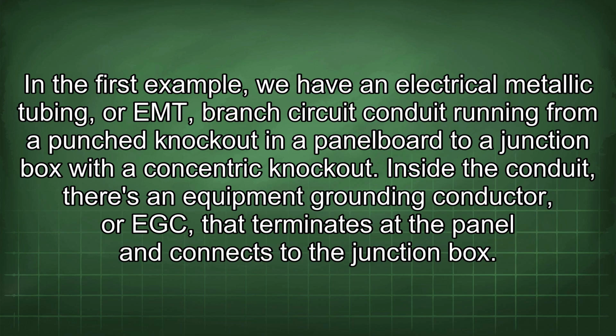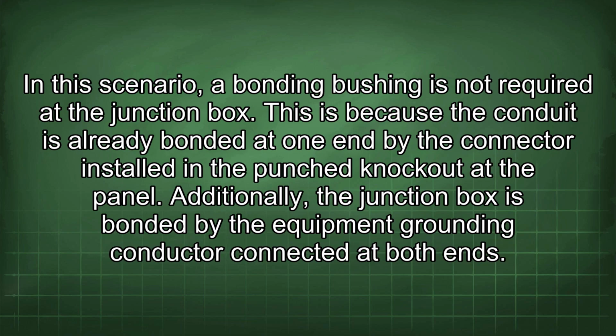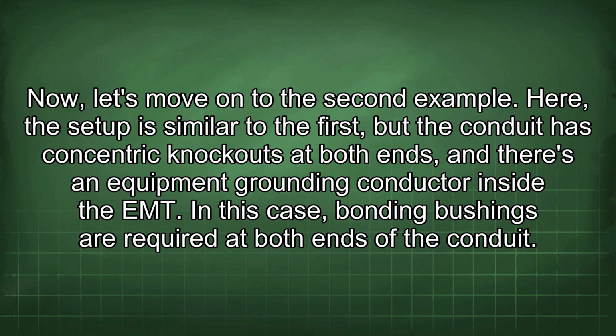Inside the conduit, there's an equipment grounding conductor, or EGC, that terminates at the panel and connects to the junction box. In this scenario, a bonding bushing is not required at the junction box. This is because the conduit is already bonded at one end by the connector installed in a punched knockout at the panel. Additionally, the junction box is bonded by the equipment grounding conductor connected at both ends. Now let's move on to the second example.